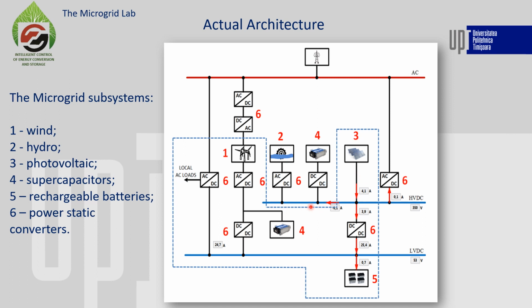To establish the stability of the high voltage DC bus in case of a sudden increase or decrease of the voltage level above the limits, an energy buffer is used. It consists of a supercapacitor and a high ratio bidirectional DC-DC converter, more exactly the bidirectional hybrid switched capacitor converter, which was presented in part 2 by my colleague Professor Dan Julia. It's connected to the high voltage DC bus. The high voltage DC bus can deliver the power either to the low voltage DC bus through this DC-DC converter, only one way, or into the AC bus through this DC-AC converter, directly.